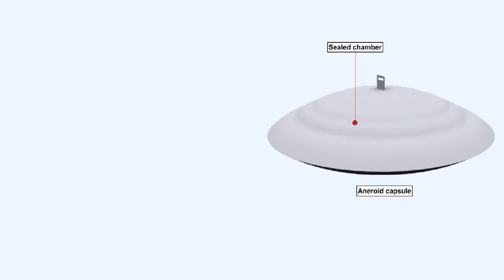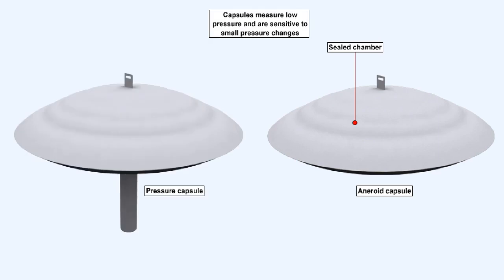Capsules are made up of two diaphragms, placed together and joined at their edges to form a chamber. The chamber may be sealed, in which case the device is called an aneroid capsule, or it may be joined to a pressure source, in which case it's called a pressure capsule. Like diaphragms, capsules are also used to measure low pressure, but capsules are more sensitive to small pressure changes.